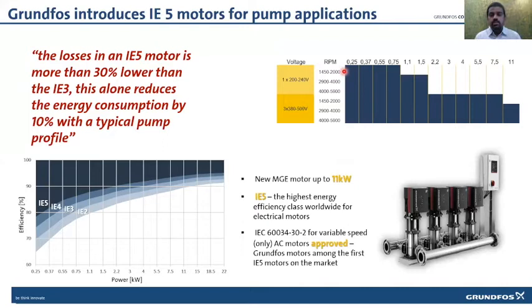On the ranges, IE5 motors for pumps are widely available up to 11 kilowatt, which is good enough for water distribution hydro booster applications. And the other advantage of having IE5 motors is, as I said, that it has integrated drives, so it saves a lot of space. And fortunately, we can run this motor at a higher RPM, so it actually brings down the pump size also for the same duty parameter which we handle with IE3 motors, with 4-pole and 2-pole motors. So that is the other savings.